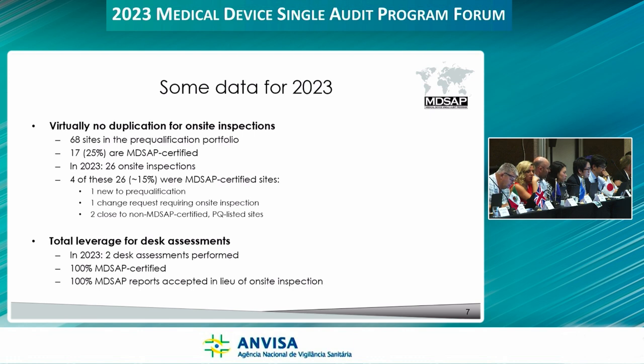But avoiding duplication also considers desk assessments, where we must do our best to leverage MDSAP reports. In 2023, we performed 2 desk assessments for IVDs - 100% of those were based on MDSAP reports, and 100% of those reports were accepted in lieu of on-site inspection. If you consider that each inspection costs the program about 30,000 US dollars, we saved about 60,000 US dollars based on those 2 reports. Remember, the program is free for manufacturers for IVDs.